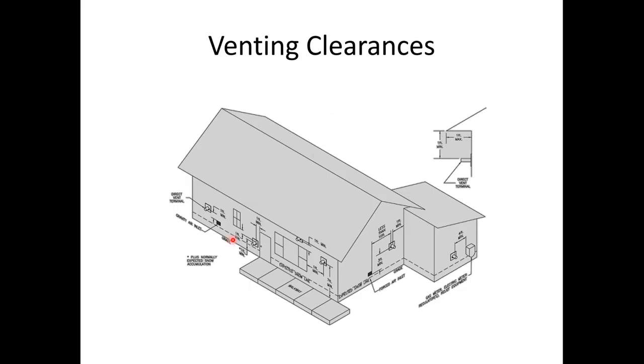Again, 12 inches above our nominal snow line. We're supposed to be 4 feet away from meters, both electric and gas, and that is due to that wonderful plume that comes out of there. All that water vapor does not play well with the electric meters, and especially some of the gas regulators. That water vapor gets inside there, gets on the regulator diaphragm, and will cause the diaphragm to pop.